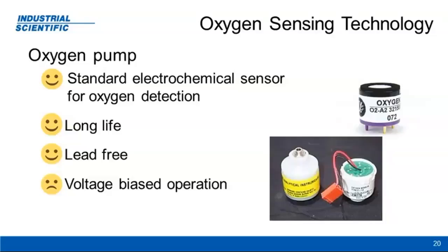They're lead-free, but these oxygen pump sensors operate on a bias voltage, and because of that they can be troublesome. If they're left off bias for a while, it takes them a long time to warm up and stabilize. So if you don't keep your instrument charged all the time, you run into some difficulties with them.